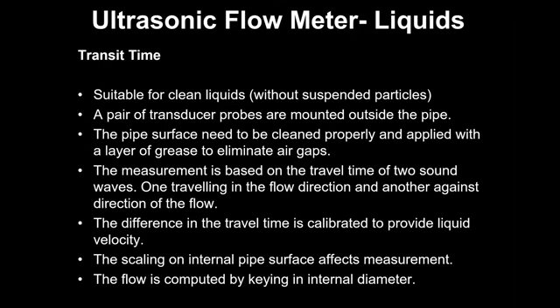So basically the principle is very simple. There are 2 probes which are to be mounted on the pipe. The pipe has to be cleaned first. You apply grease to eliminate any air gap, because that is required. If there is an air gap, the signal won't transmit through. So these 2 probes will emit an ultrasonic signal. Each probe, or transducer, is a receiver and emitter. So it will emit the sound, and it will also receive the sound.